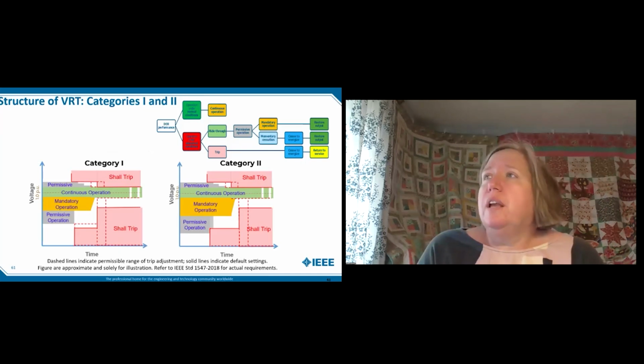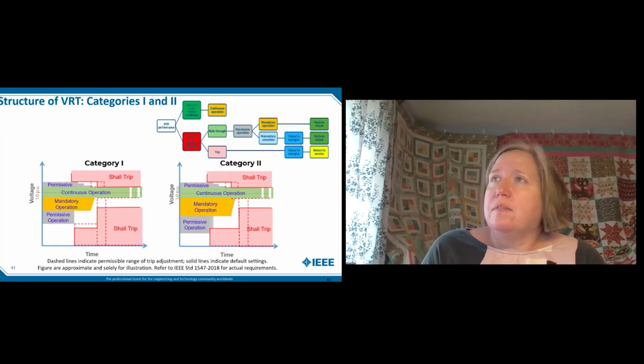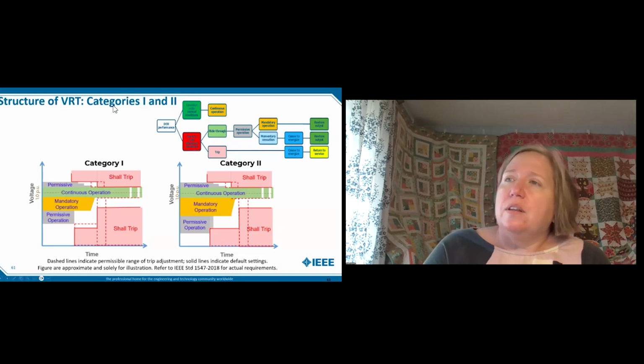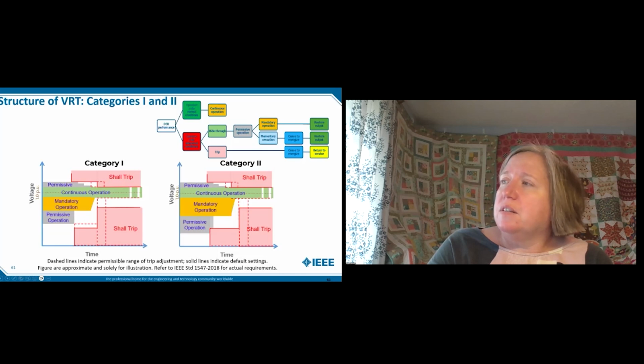So looking at the structure of voltage ride-through. If we look at category 1 versus category 2, you can see that the overvoltage permissive is pretty much the same. The continuous operation looks the same. But as you look at the under voltage ride-through, category 2 goes a little deeper. The permissive operation goes a little deeper. And then you can see the shall trip ranges, where the solid lines are the default settings and the dotted lines are what you can adjust to.